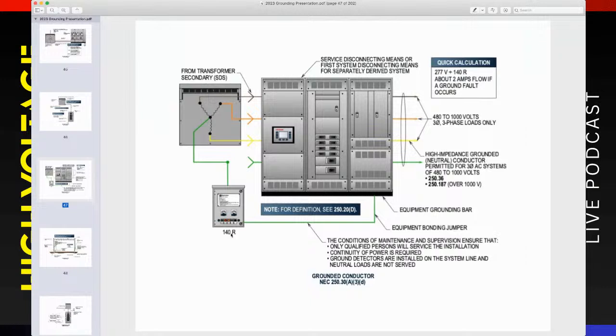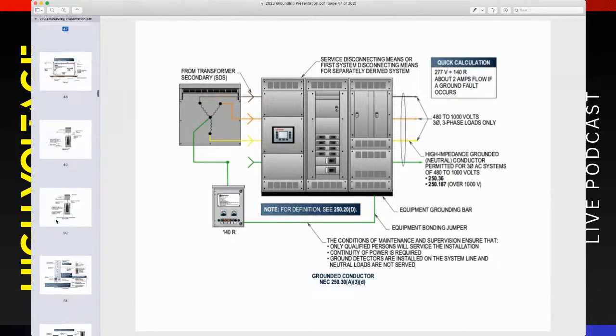We show you the impedance device here is 140 ohms. About how much amperage is going to flow through there? You've got 277 volts flowing across that—divide it by 140 ohms, and it's going to tell you there's about 2 amps of ground fault current flowing across that. Go look at these other publications, you won't see this.